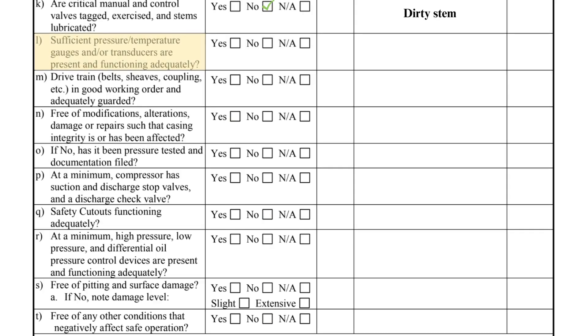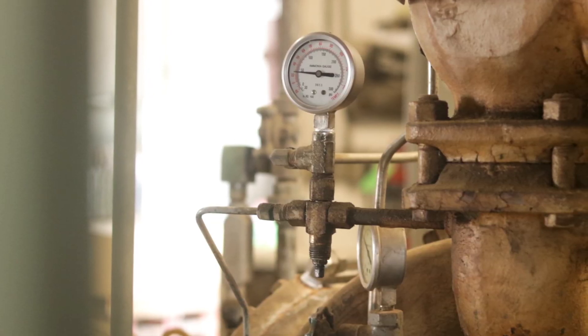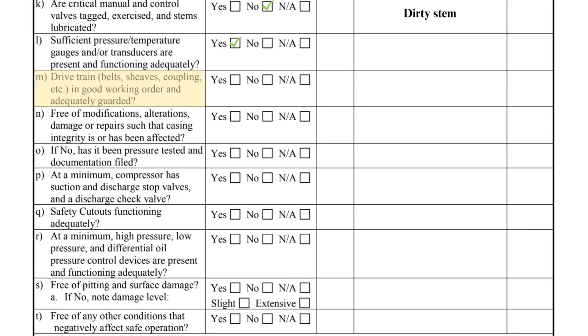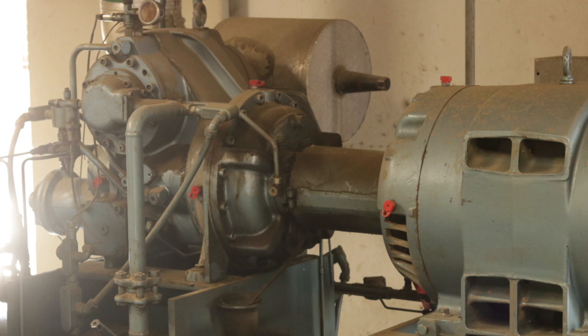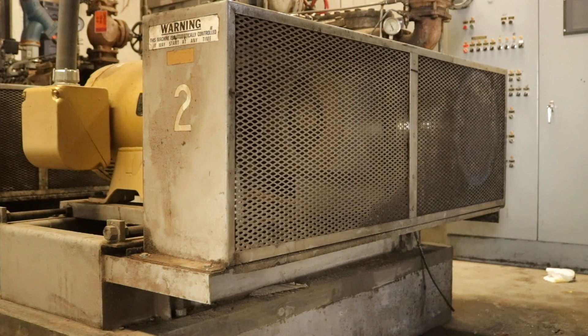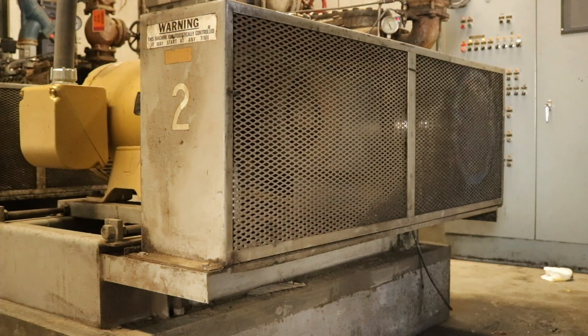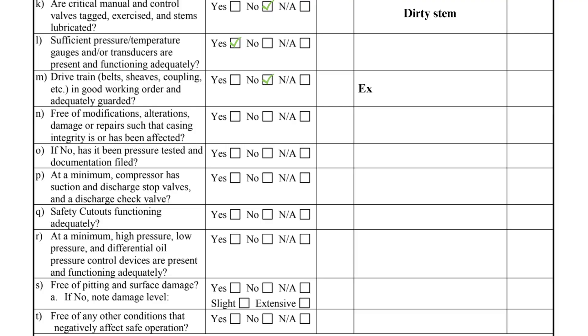Item L: compressors must have sufficient instrumentation for monitoring operating conditions — analog gauges or microprocessors to observe operating parameters. Item M pertains to the drivetrain. It is important to check that the rotating shaft is properly guarded to protect employees from injury, and belts and sheaves on belt-drive compressors should be inspected for deficiencies. The excessive dirt on and around the screw compressor shaft must be cleaned up.